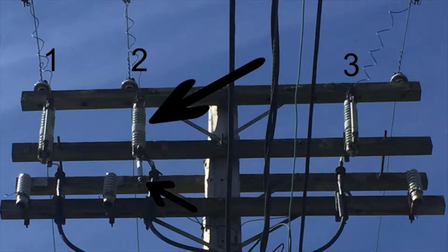There's two things. We had a partial power loss about a couple months ago, when a squirrel hopped on the line over here and knocked one of the phases out. In that case, anytime the power goes out, make sure the drivers shut the power off the compressors as soon as they can, because if you have two phases going on a three-phase motor, you'll burn one of the motors out. I don't know a whole lot about it, but running a three-phase motor on two phases just burns the motor out.